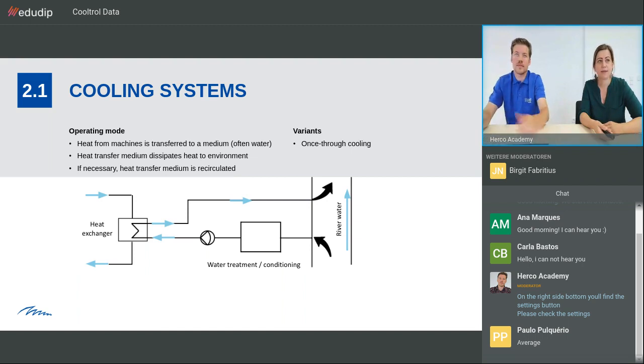So first of all, cooling systems. In general, a cooling system is always about dissipating heat that comes from industry, let's say, or from a building. So let's say we have an industry, we have machines, and we need to transport the waste heat away from the production. This is done using a medium, which is very often water, because it's relatively easy to use. And the simplest system that is shown here, the most basic one, is once-through cooling. That means water is taken from a water body, let's say a river, can also be a lake, for example, or even groundwater. If necessary, that water is conditioned or treated by filtration, for example, by softening, and is pumped over a heat exchanger where it takes the heat from the machinery of the plant, and then this water is again sent to the water body it came from.